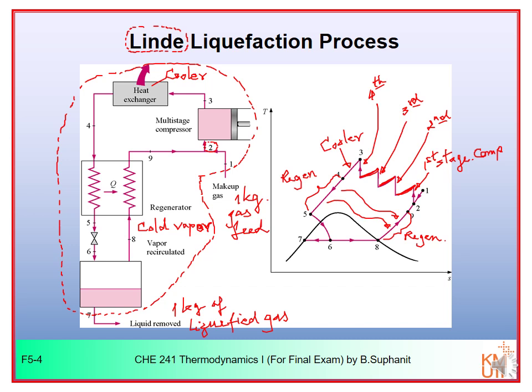After exiting the regenerator, the gas is flashed through an expansion valve — five expanded to six (JT valve). At point six it has entered the two-phase region as a vapor-liquid mixture. You separate vapor from liquid using a flash drum: number eight is vapor, number seven is liquid product. The cold vapor at eight passes through the regenerator, exits at nine, and mixes with makeup gas to become point two — the compressor inlet again.